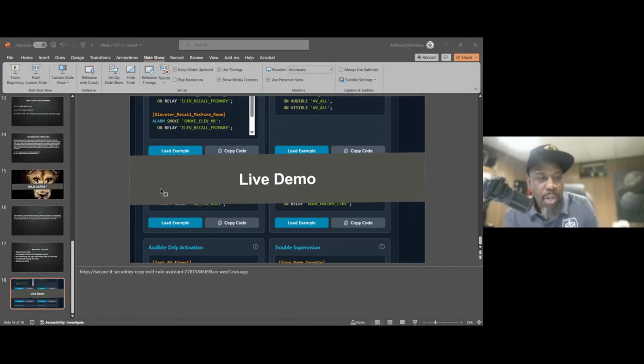So on the AC failure, we have to write AC fail, and then the label is AC brownout star. When we go inside the object labels, you'll see why they're defining it as star. So we send in messages, the activation message and the restore message. Same thing here with the ground fault. So we're defining all these things in a Modcom, especially if you're using Contact ID. And if you're using just zones, these are all just to be grouped up into particular zones, like a pull station zone, smoke zone, trouble zone, things like that.